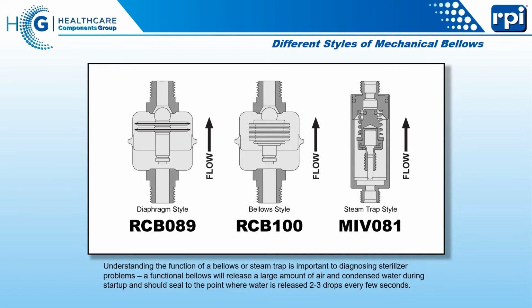So this was the original style. Somebody realized that you're taking those two plates and stretching them out a lot, and there's a lot of metal fatigue there - maybe that wasn't the smartest idea. So they came up with this upgrade. It has 7 plates, and each one works exactly the same, but each plate stretches out a little bit less, so there's less stress on the entire assembly. Because it stretches less, this is actually a more accurate system - you can get finer temperature control with it.